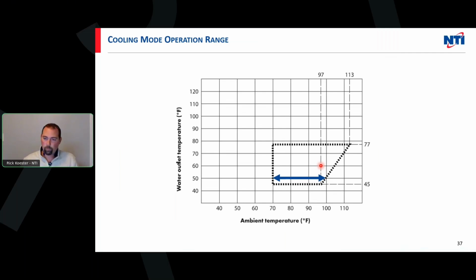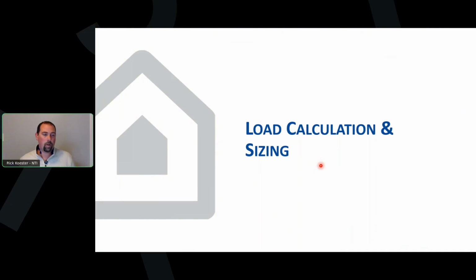If we're talking cooled water, which is a very cool application, if you've not done one yourself, we just have to make sure we have good dehumidification somewhere in the system. We don't want to run chilled water through a radiant tube or something like that and not have dehumidification. So that's a whole other animal.